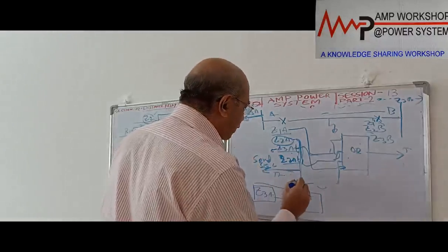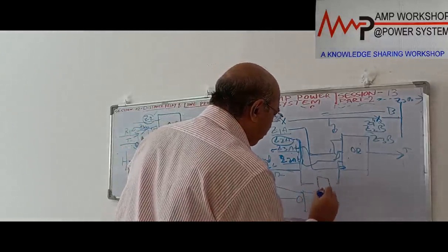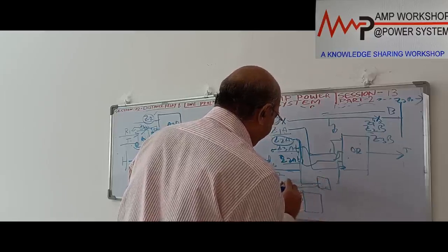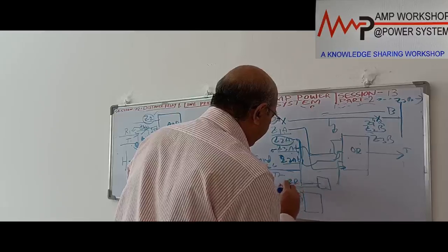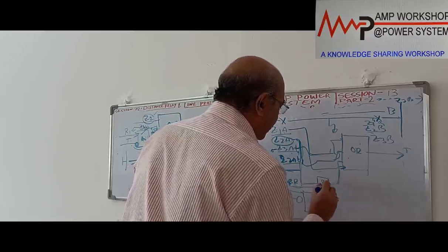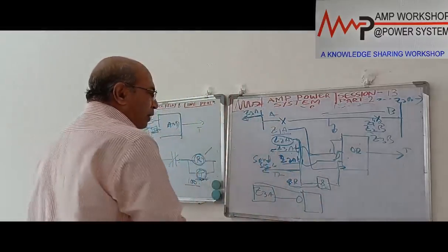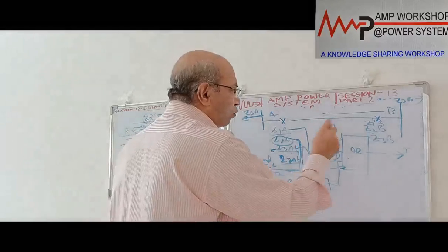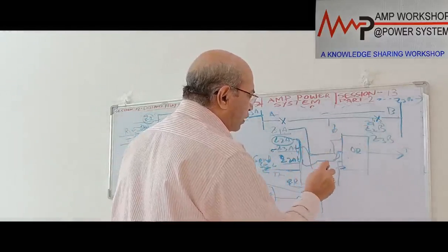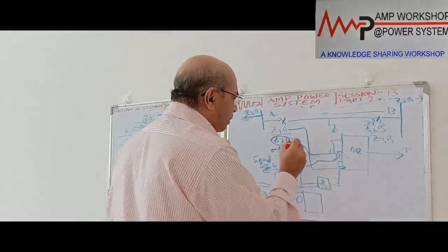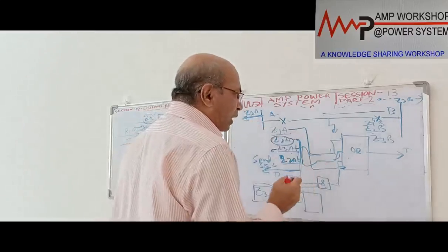So this is a Z2, and then this is a gate over here. Here is Z2, and this is the signal received, PR, permissive receive, and this is an AND gate. Then it will give the trip command. We can write it in this way, in gate form. Zone 1 tripping is instantaneous, zone 2 and zone 3 are time delayed, and when zone 2A operates, another tripping is there, that is end zone clearing expedite.